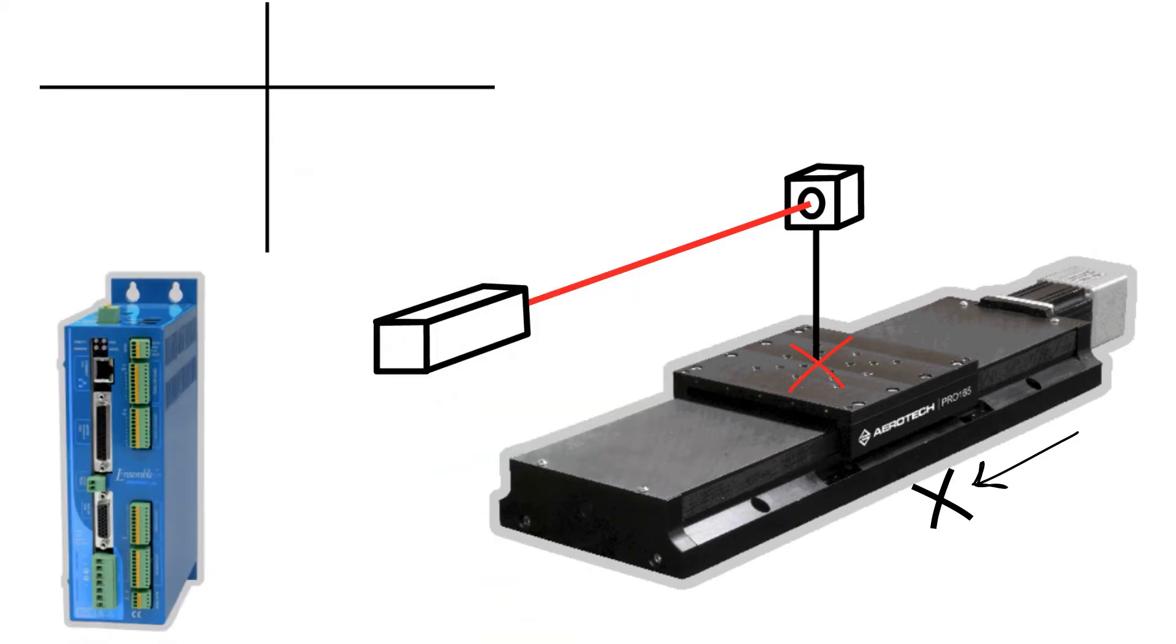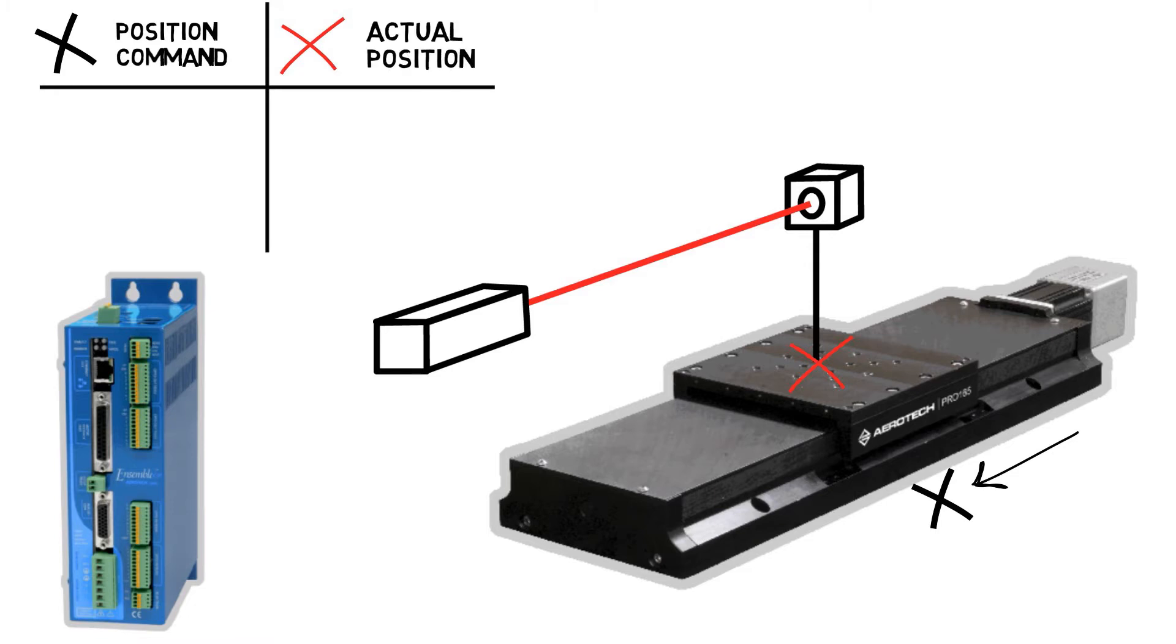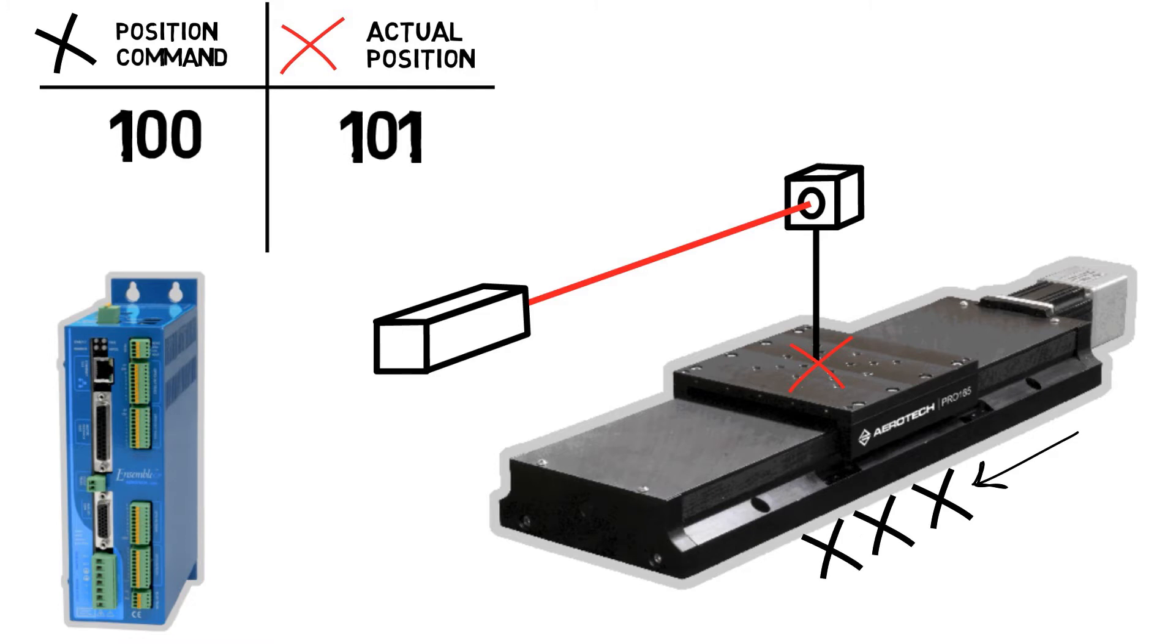The interferometer measures the final position of the stage, and we can then record the difference between the actual final position and the position the controller commanded. We can then repeat this procedure for a range of points throughout the travel of the linear stage.